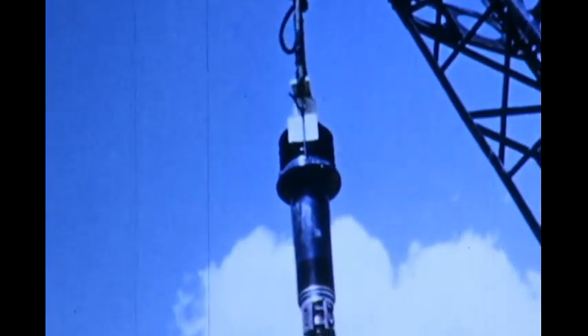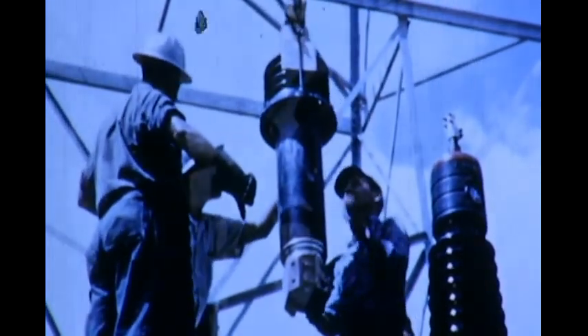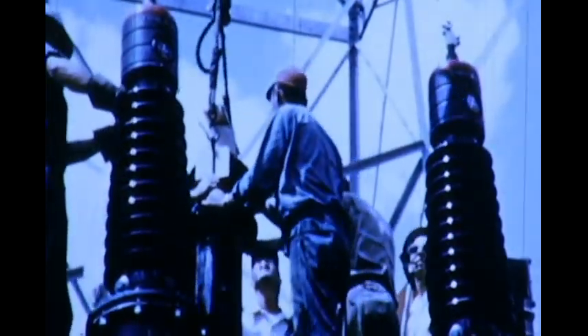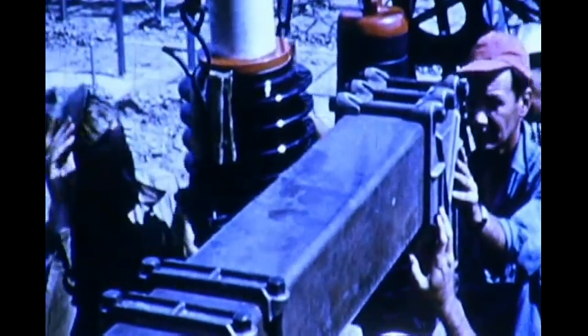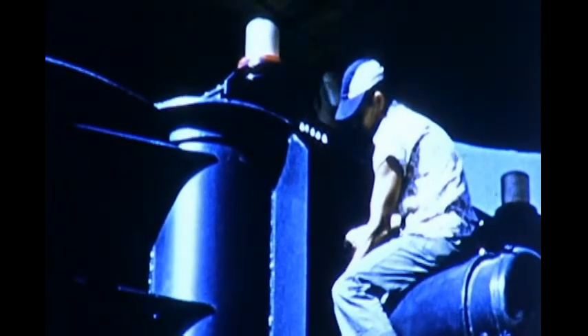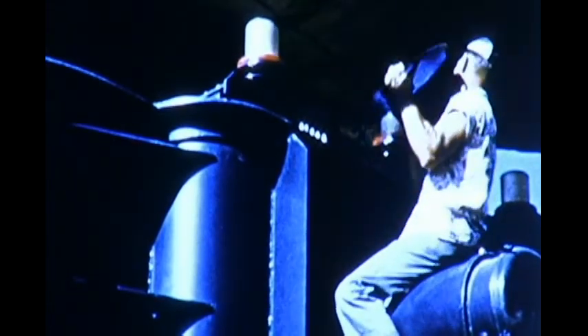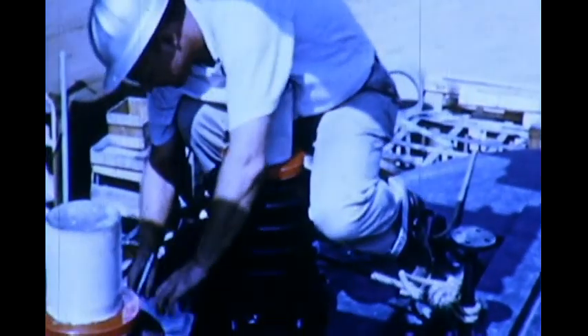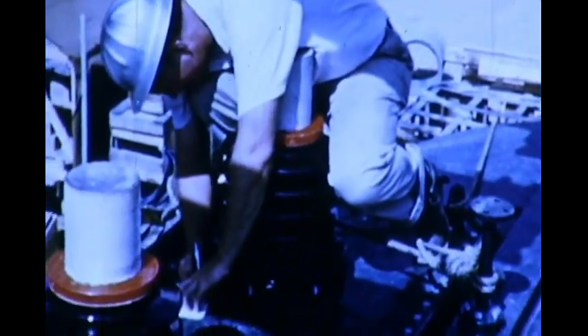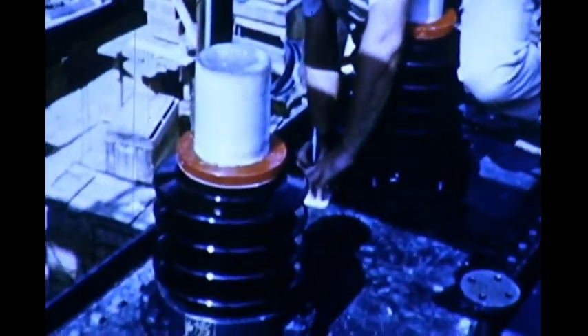The procedure here is much the same as for the high voltage bushings, with the crane guiding them carefully into place. The wooden blocks protect the porcelain from possible damage by the cables. Internal connections to the low voltage bushings are made through manholes in the side of the transformer tank. The rectangular plate to which the low voltage bushings are bolted is made of non-magnetic steel to prevent overheating of the cover by the intense field around the high current bushings.